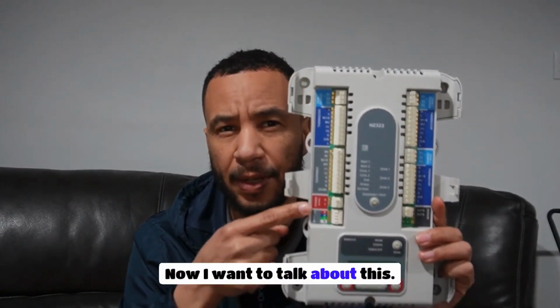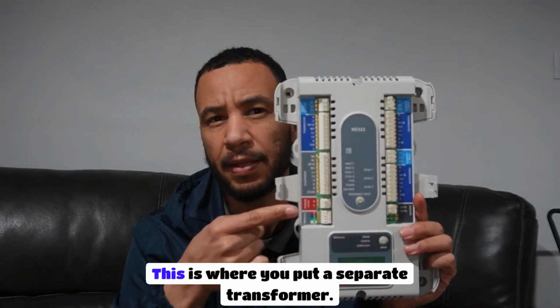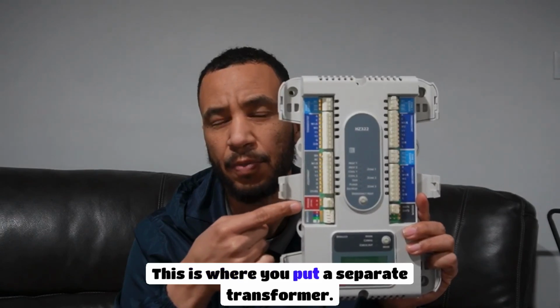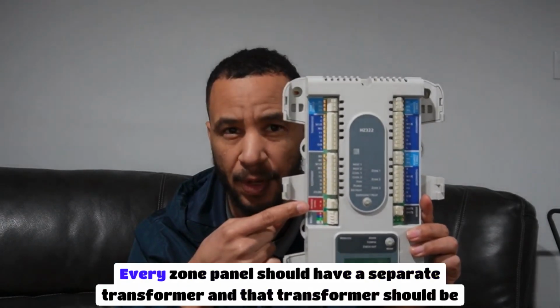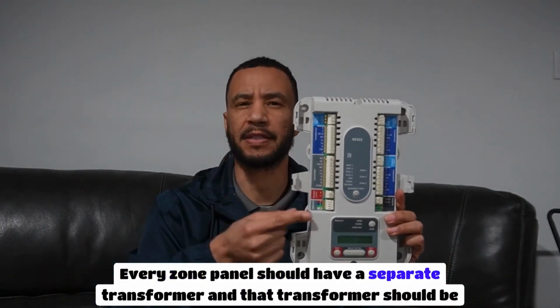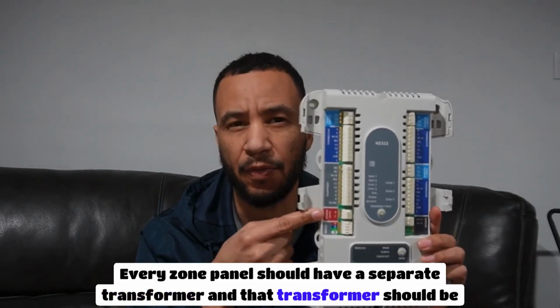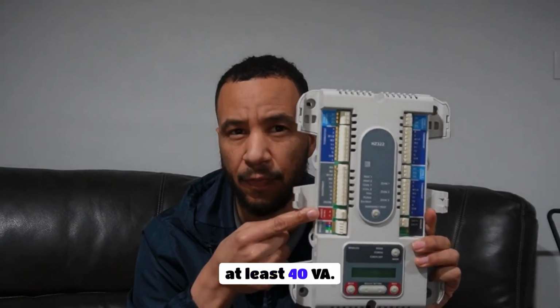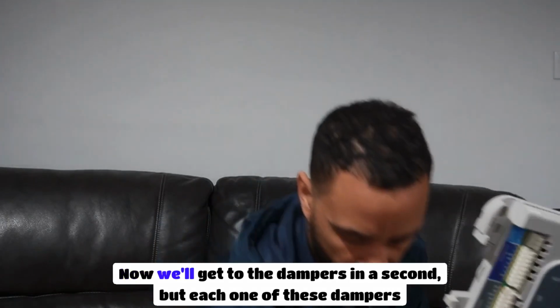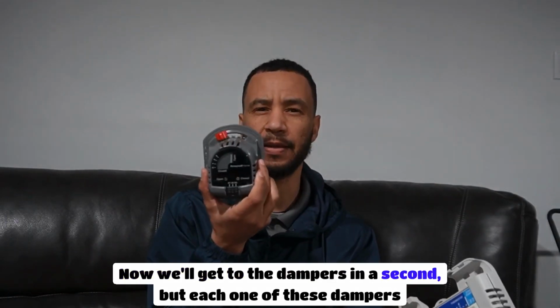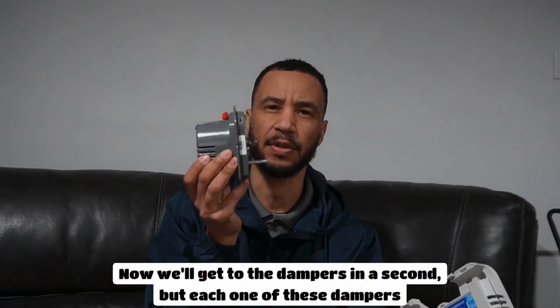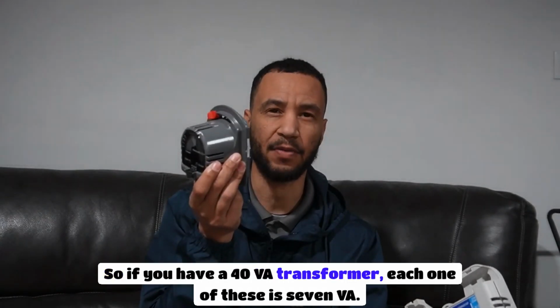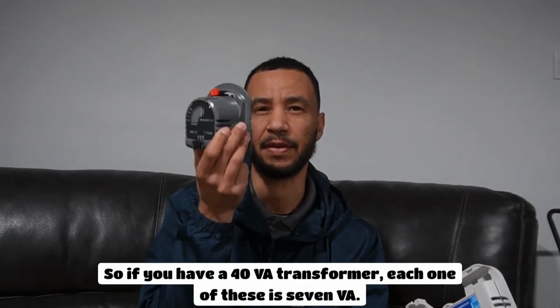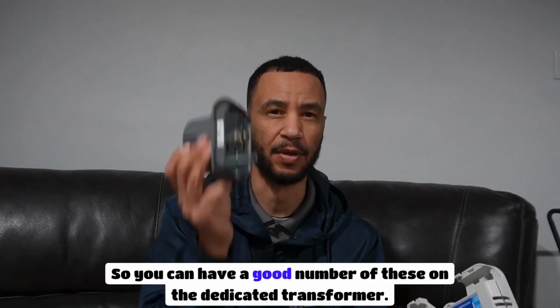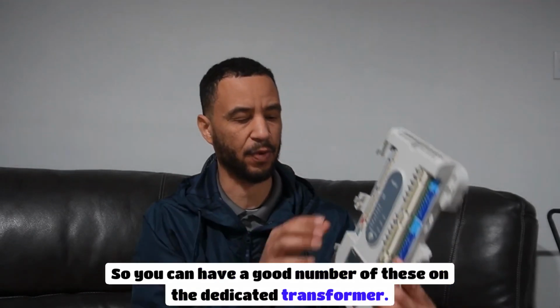Now I want to talk about this. This is very important. This is where you put a separate transformer. Every zone panel should have a separate transformer, and that transformer should be at least 40 VA. Now we'll get to the dampers in a second, but each one of these dampers pulls 7 VA. So if you have a 40 VA transformer, each one of these is 7 VA. So you can have a good number of these on that dedicated transformer.